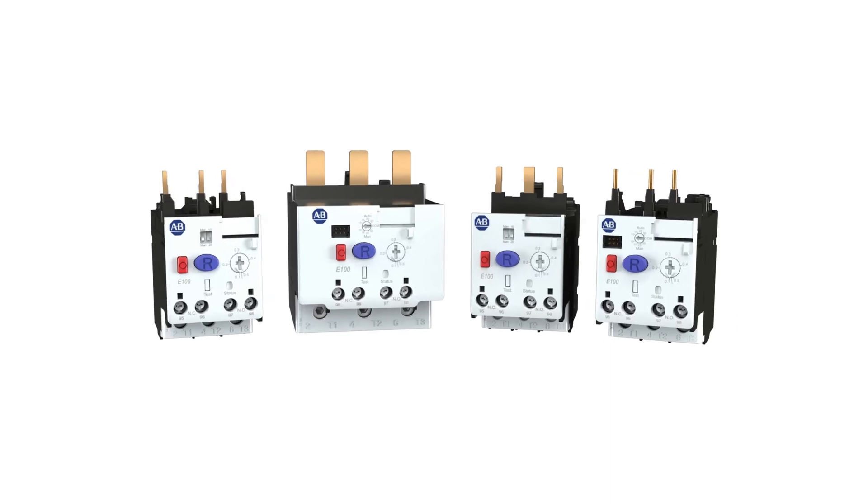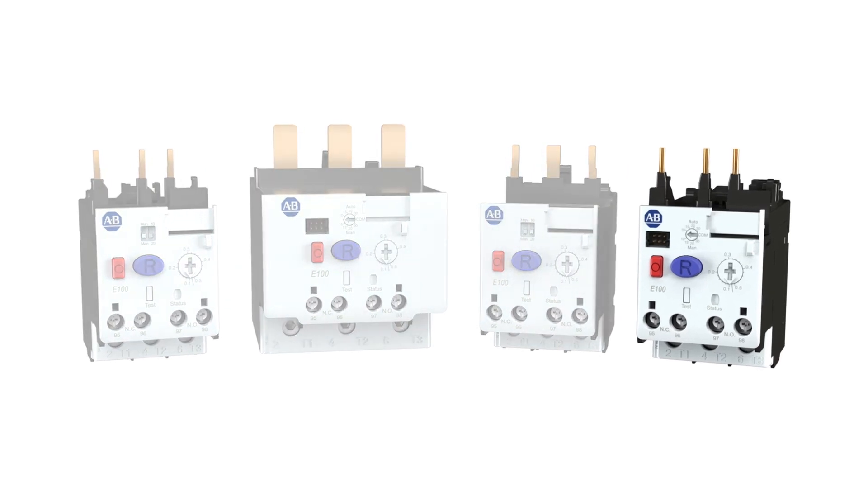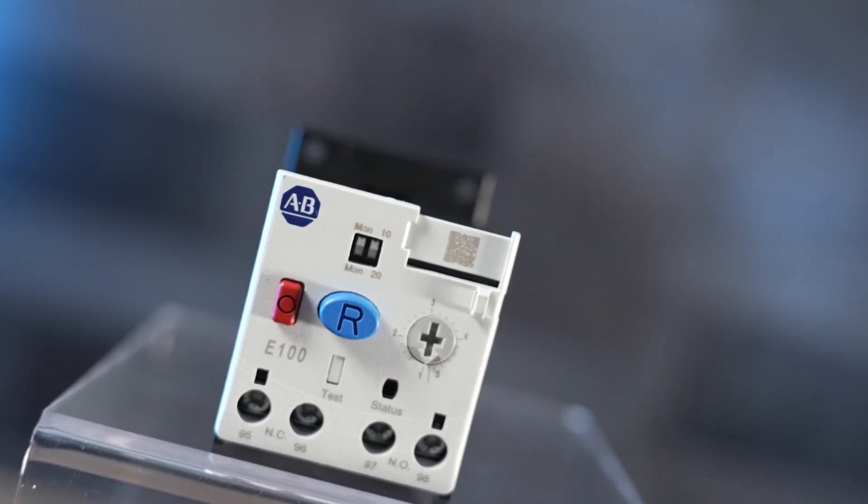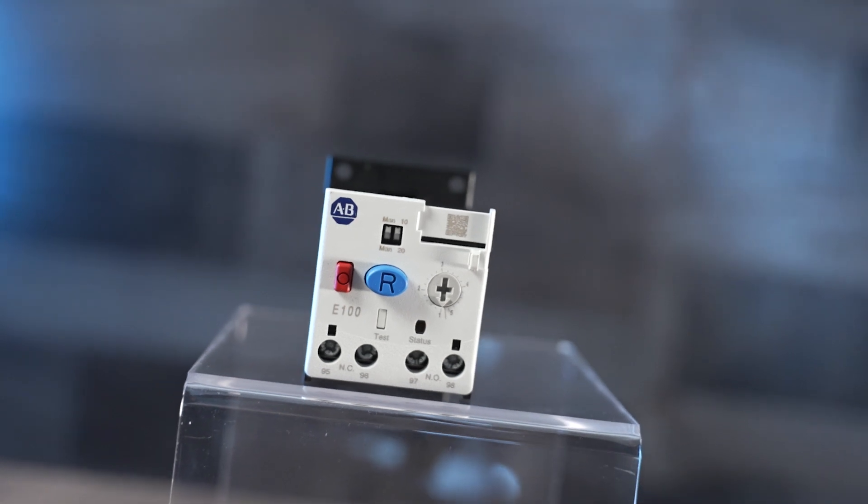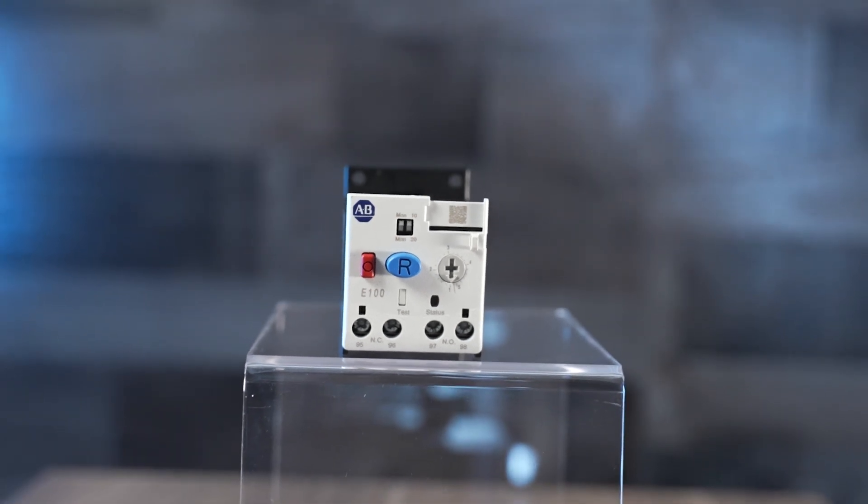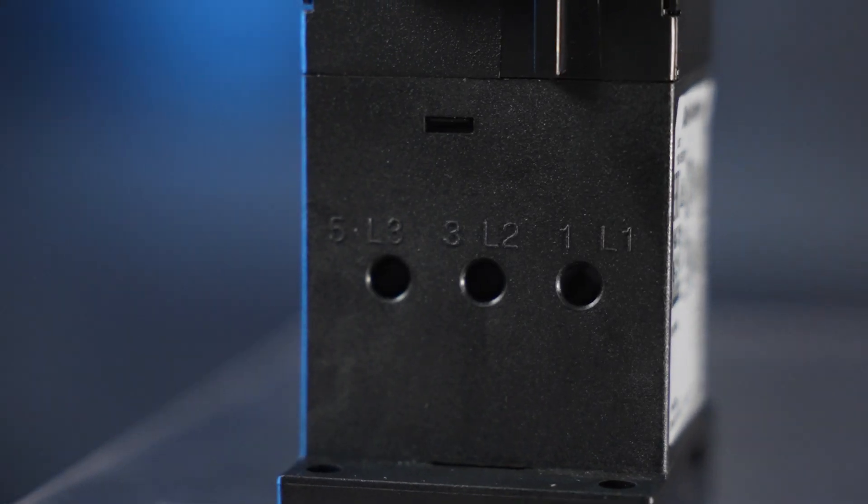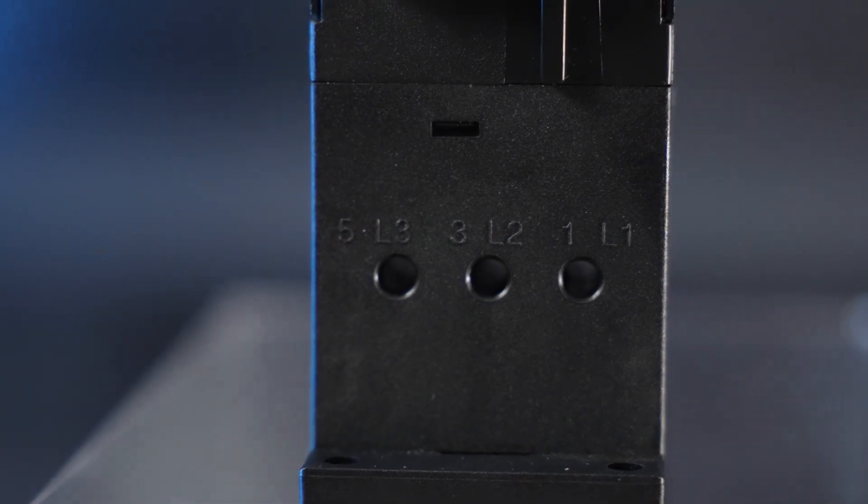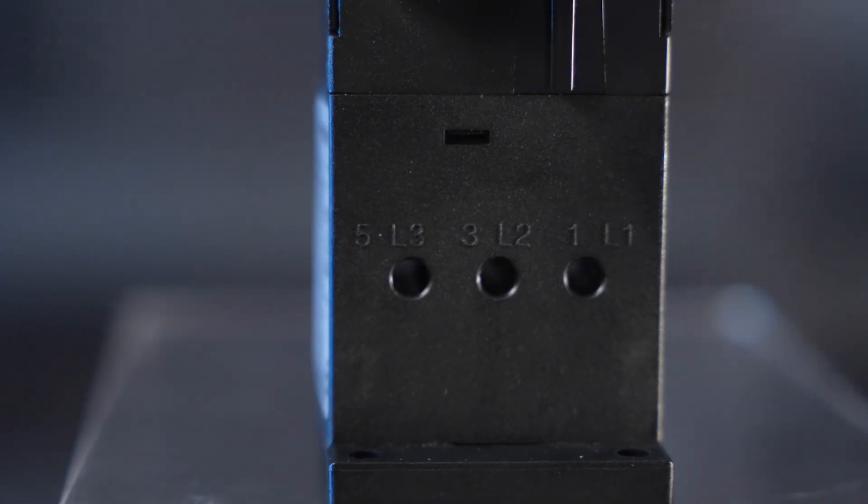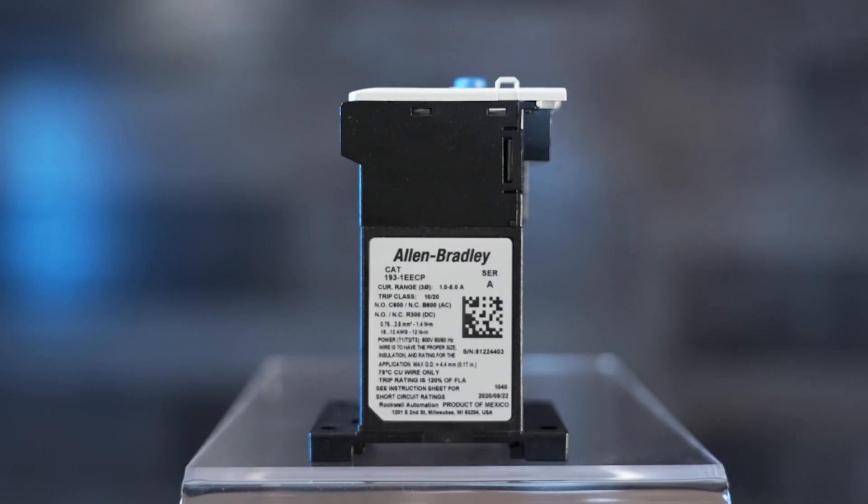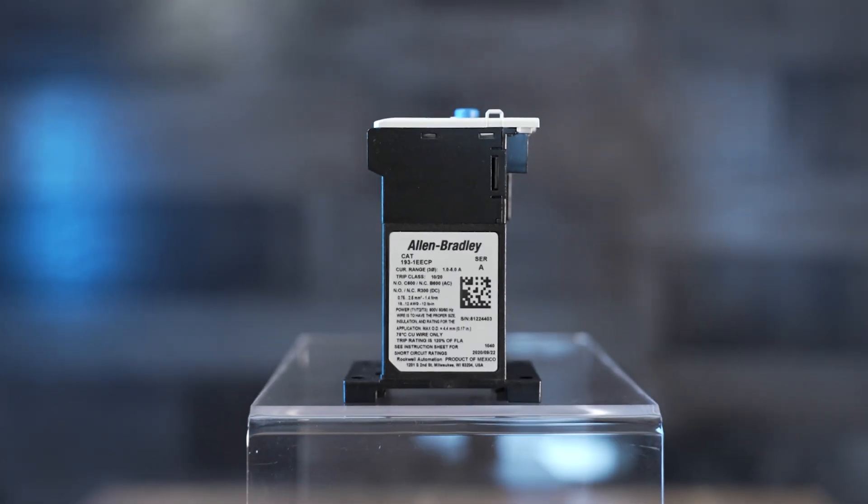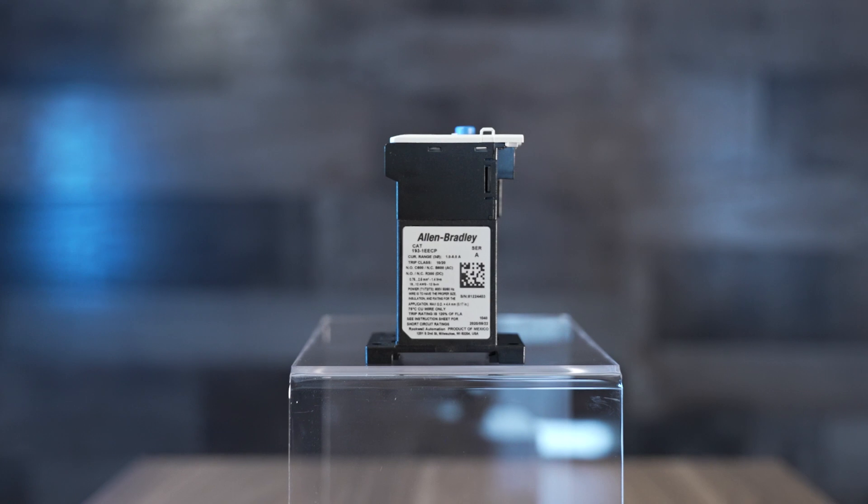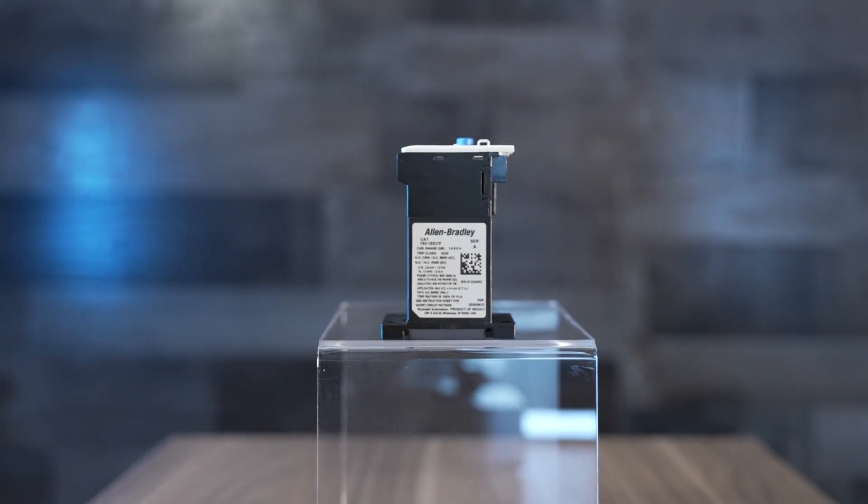Let's take a closer look at the E100 overload we have here. This is an electronic overload. These contrast with traditional overloads employing bimetallic strips that expand and contract at different rates to open and close the contacts. More specifically, electronic overload uses secondary currents off the current that's already passing through the device to power electronics when current is too high. This serves as a self-powered design needing no auxiliary power to work.